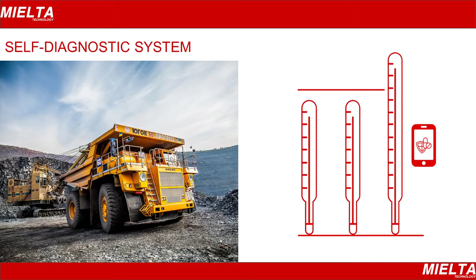It's a kind of special code, like other analog sensors send. However, unlike its competitors, the Fantom sends not only an error code but also an error value that can be used to determine the reason for going out of range. This may be a change in fuel quality due to possible impurities, incorrect calibration, or various liquids entering the tank, including water. The sensor will not stop measuring even if there is water in the tank, and can give you an estimated value of the water level.